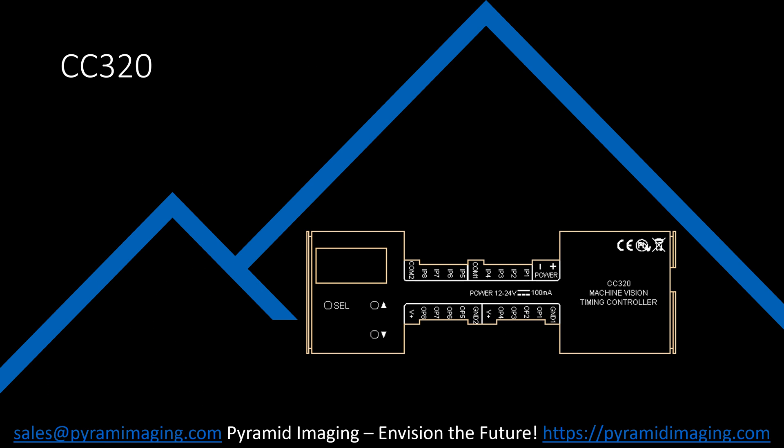The CC320 has eight optocoupled inputs and eight optocoupled outputs. They are divided into groups of four, which share a common ground node. The outputs are open drains. Two low power logical high outputs are provided to feed pull-up resistors.